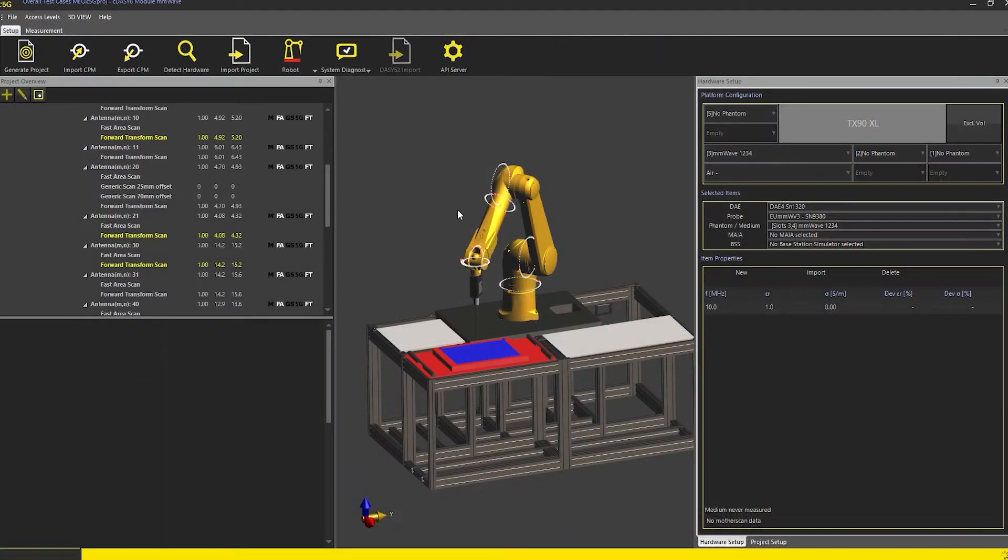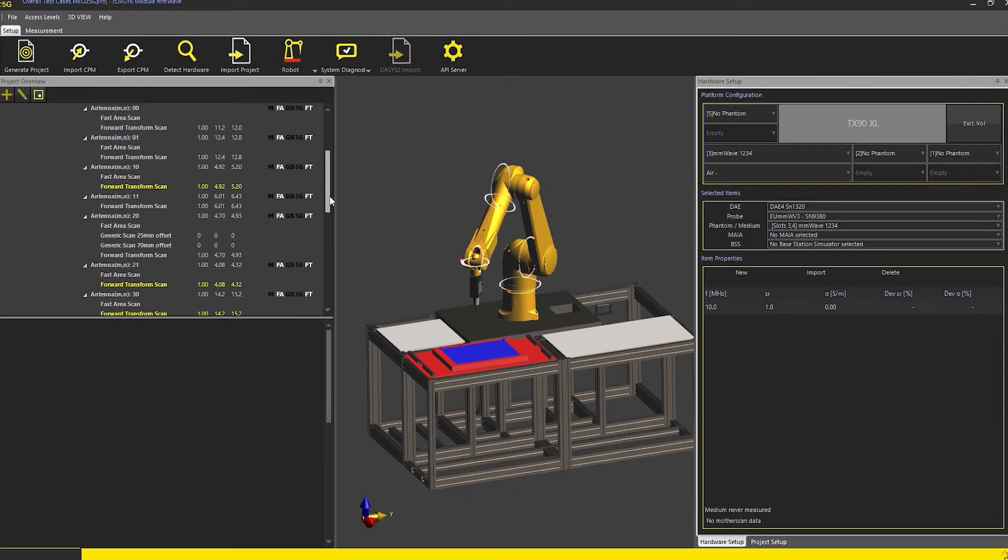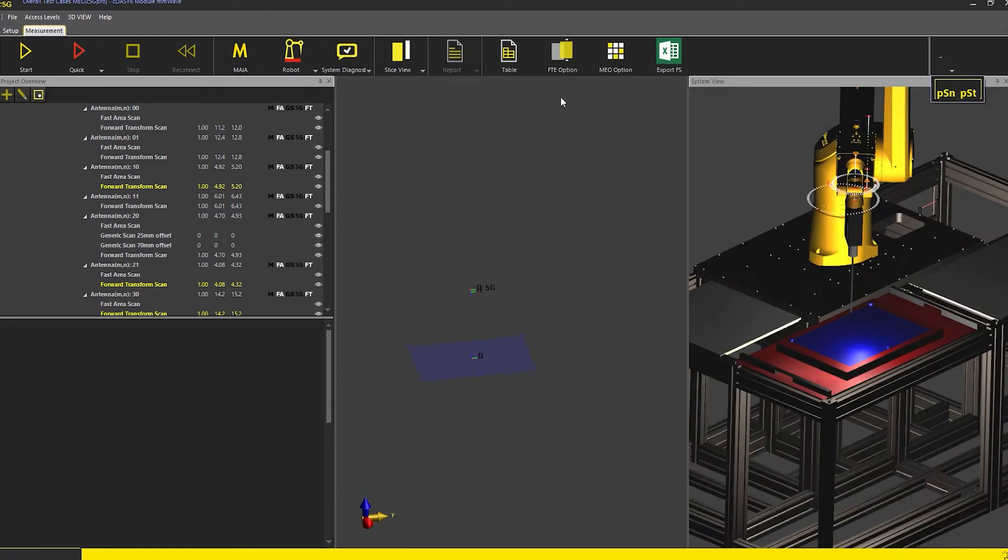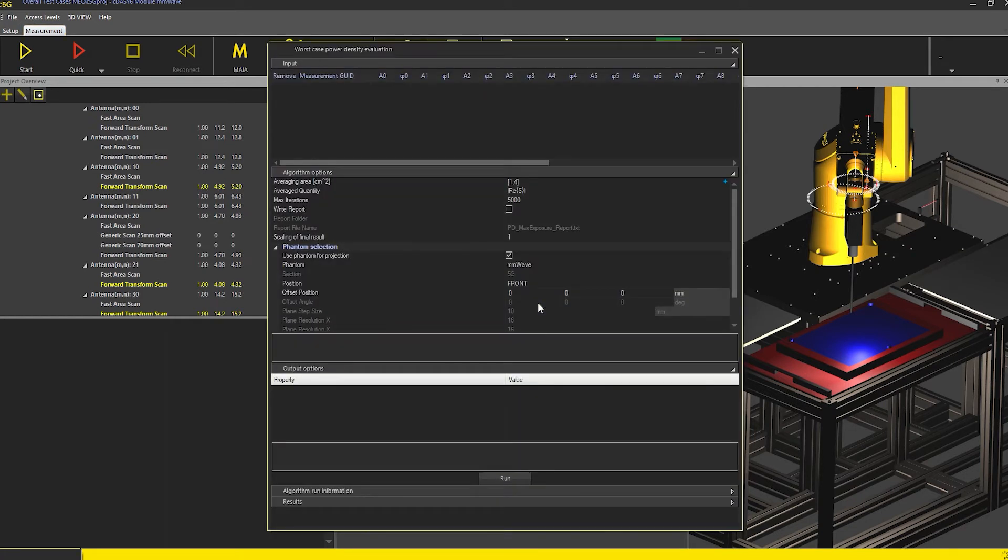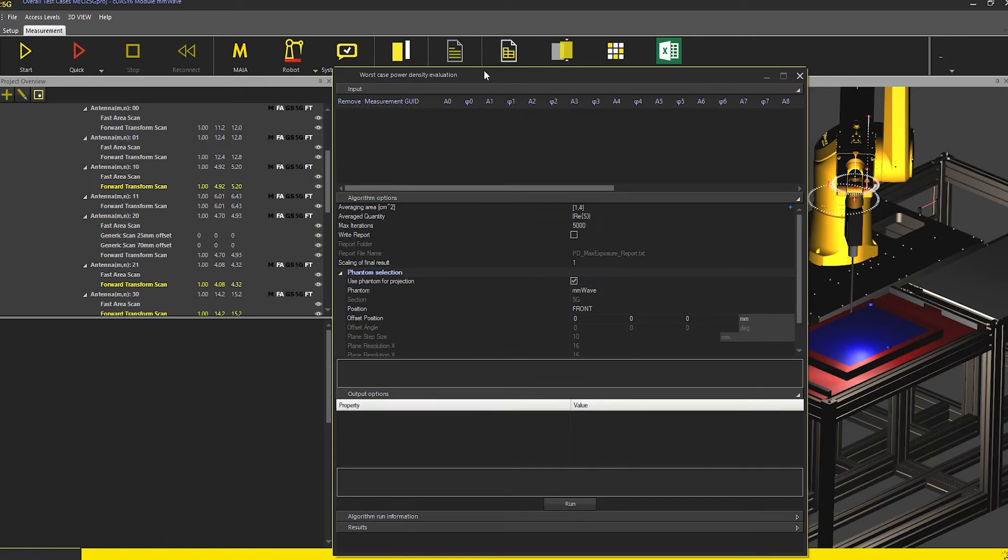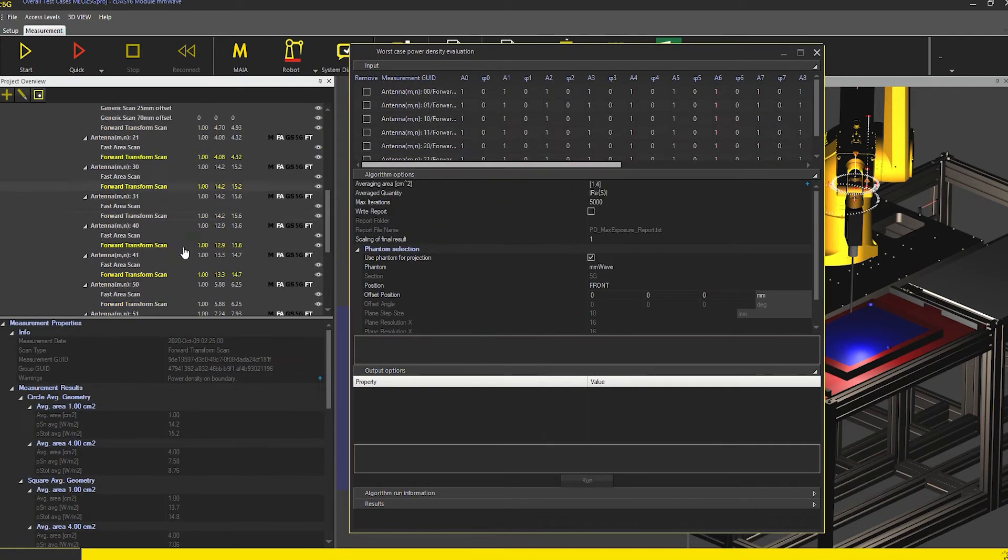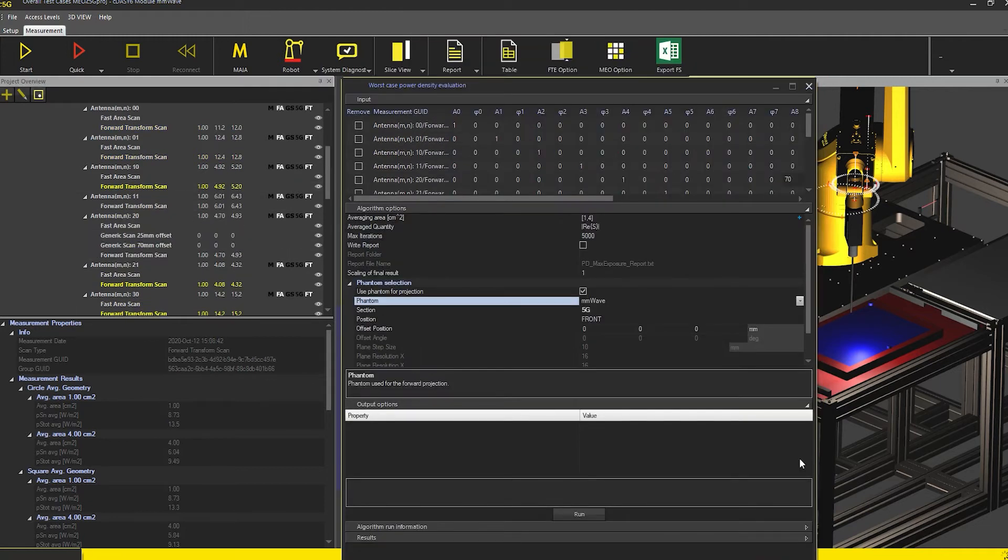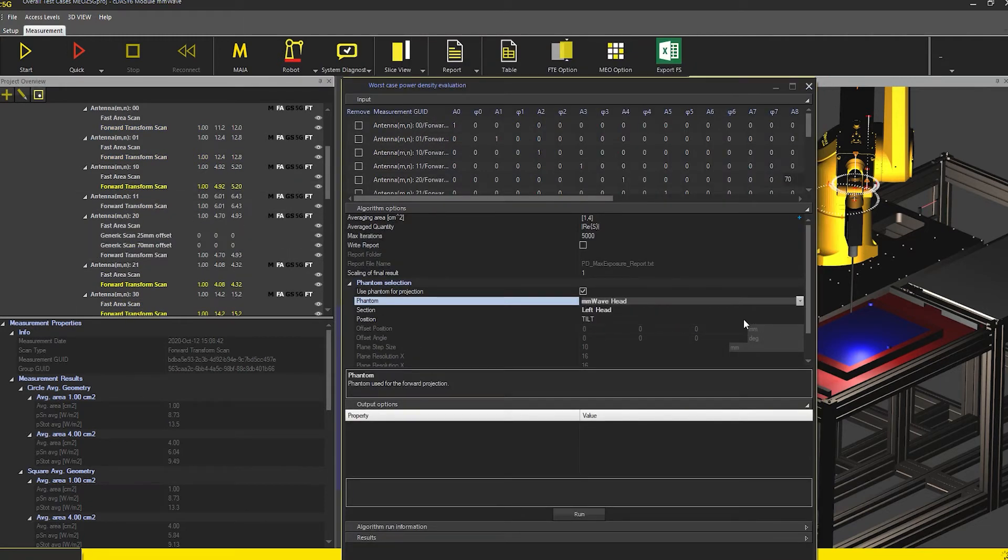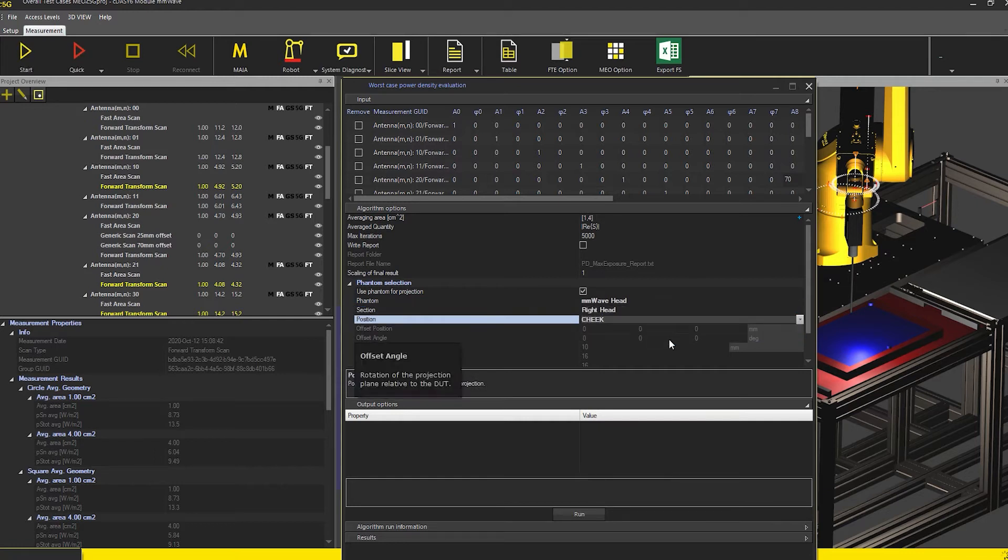To evaluate the worst case, I start the maximum exposure optimizer or MEO option and add the 17 measurements to the MEO window and define the phase and amplitude values for each of the measurements. Next, I select the SAM right head and flat phantoms to evaluate the worst case power density and start the optimizer.